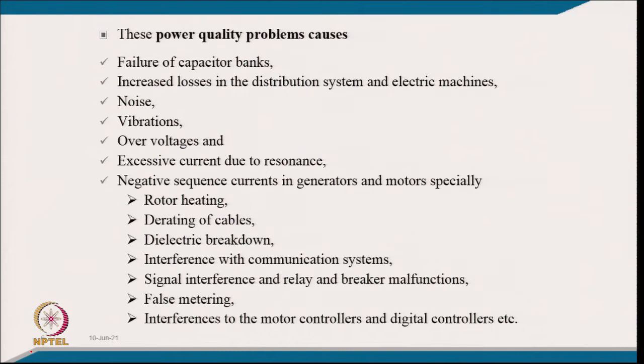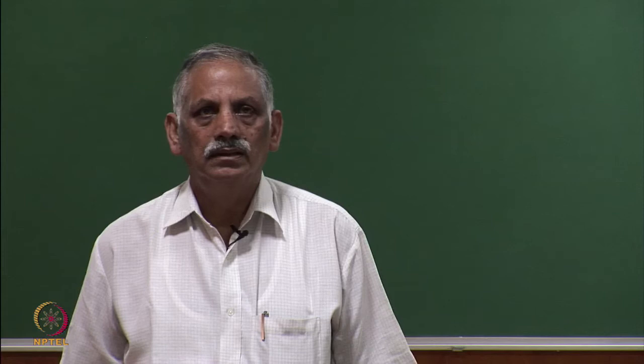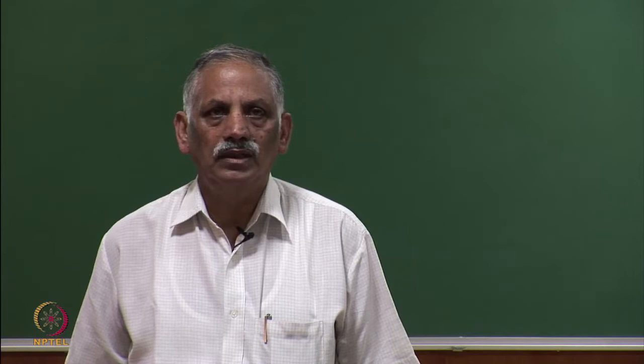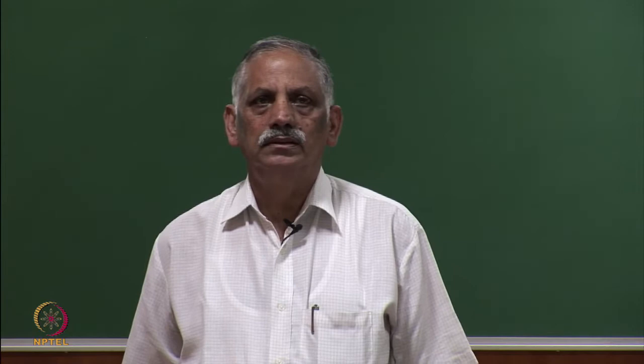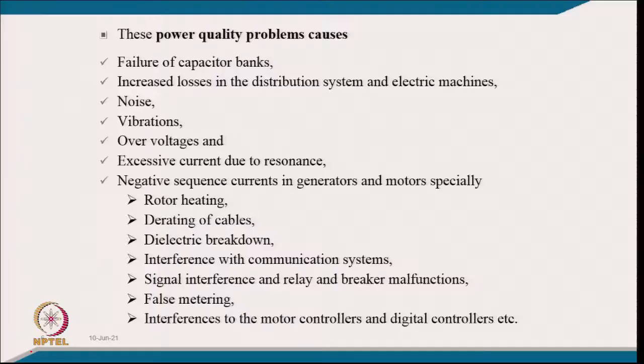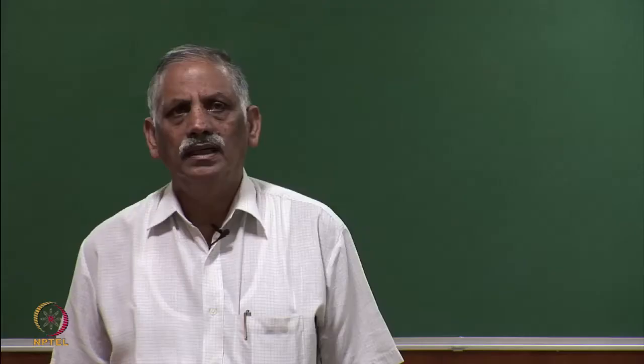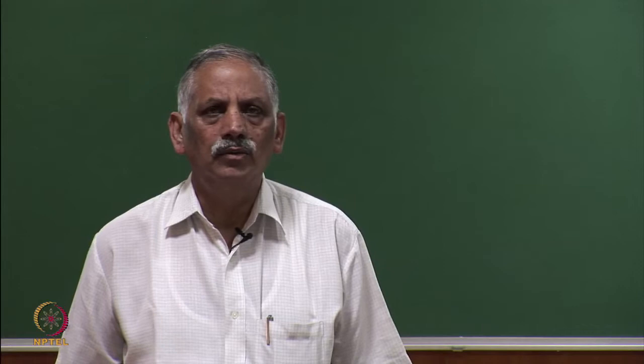Harmonics also cause increased losses in the distribution system and electrical machines. In electrical machines, these power quality problems produce harmonic torque, then vibration, and noise. It can also cause overvoltage and excessive current due to resonance — a phenomenon between source impedance and the capacitor connected at the point of common coupling.